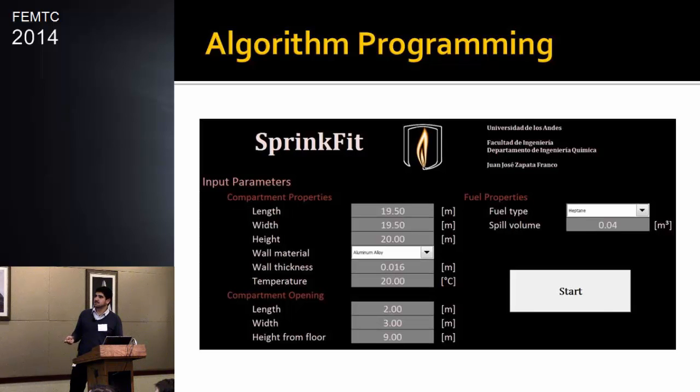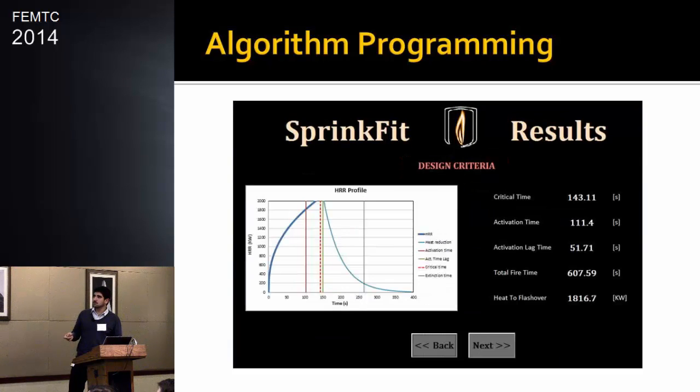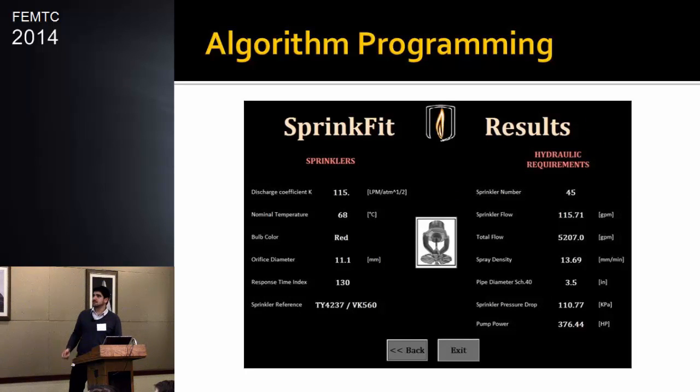I used the first example, the experiment, to test it. And it's going to show you the scenario simulation, the properties. It's going to show the critical time, so we take that into account. It's going to show how the system is going to work, the critical time, the activation time, lag time, total duration of the fire, and the heat to flash over. It's also going to suggest the properties of the sprinklers and the hydraulic requirements, such as the number of sprinklers depending on the area, also some references, and the pump powers, pressure drop, well, everything related to the sprinkler system design.